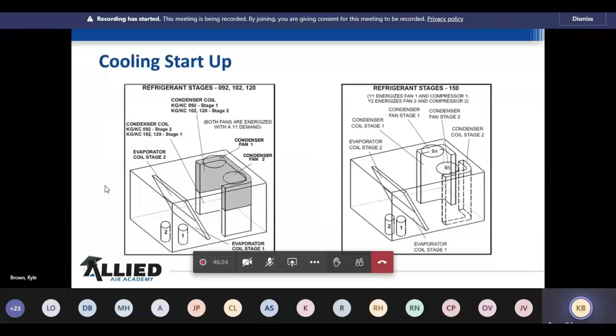Because, and I put these 2 examples in here, if you look at both of these, the stage 2 evaporators are on top, the stage 1's on the bottom. There is no lead lag on these. Okay, this isn't like some of the chillers you may run into or some of the other equipment. So stage 2 is always going to be on the top.